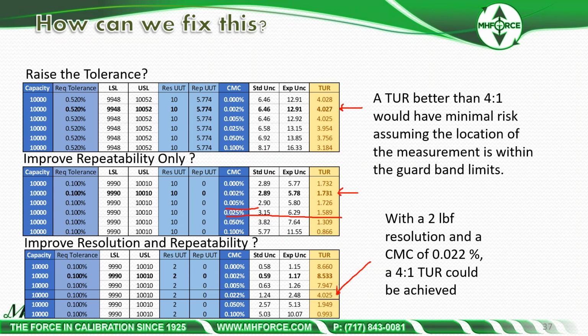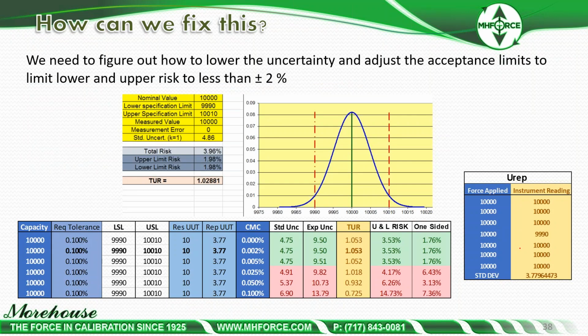A lot of people with a military mindset still want the 4-to-1, and they're able with secondary standards to achieve about 0.2 to 0.3. So if they get everything together, it's really the scale. The whole thing in this is it's the device. You're just not going to be able to make that statement of conformance or compliance with this device if you have that resolution of 10 pounds and your repeatability is what it is. It's just very, very difficult using the current equipment that's out there. So what else can you do?